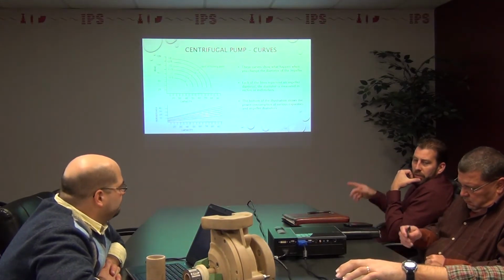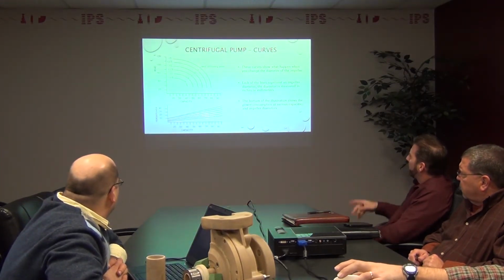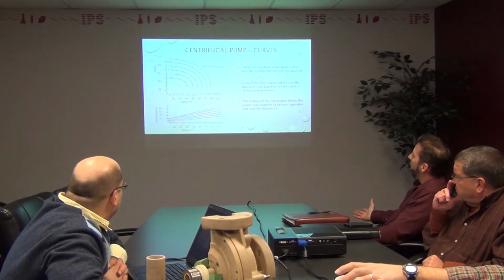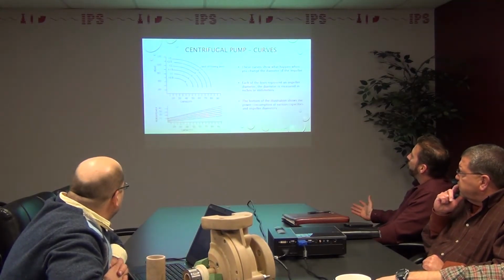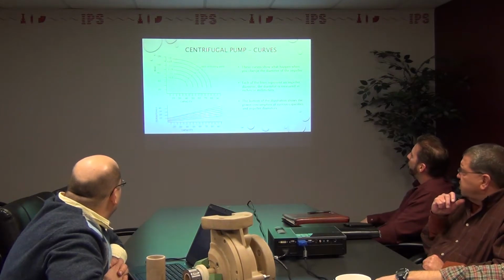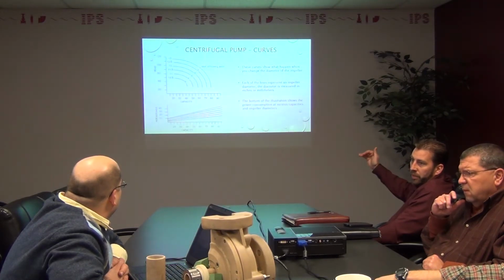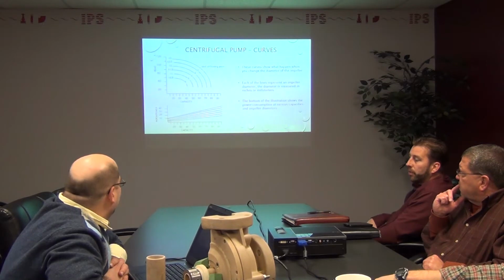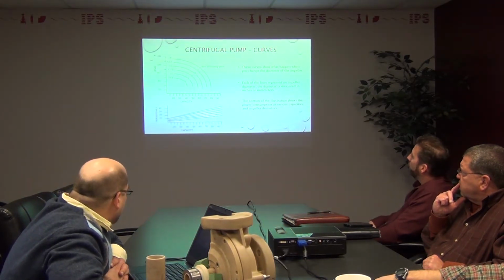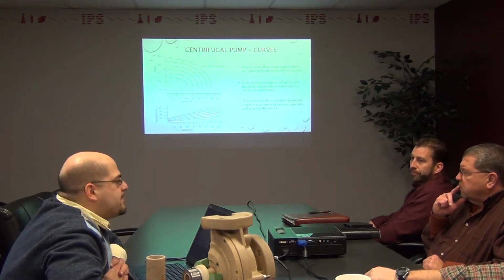So, but similar, yes. I had a question, looking at the horsepower again, like Dan said, you go with 60 gallons per minute, and I forget what he said, 80 foot of head. You come down for your horsepower. You stop at that first line, the top line. What are all those other lines? They correspond with the impeller trim. So the bottom one would correlate with the 10.5, okay, 11. Six lines up top, six on the bottom.